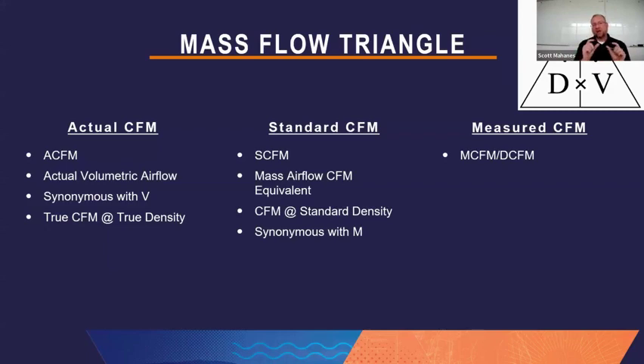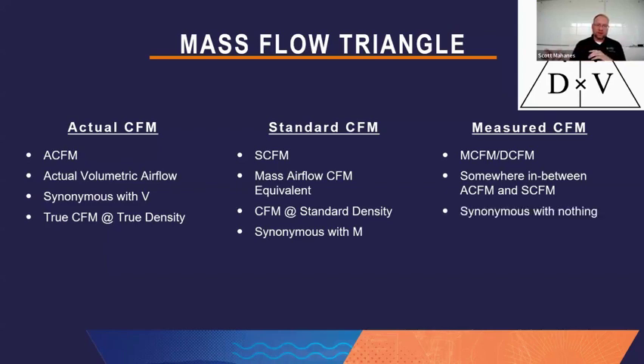And the displayed value that's on that meter doesn't always mean that's exactly what I have there, because if the temperature is different, then I definitely have to correct for that. And so oftentimes our displayed values on our tools are not exactly an accurate measurement because we have to consider the density at the time we do that test. And what ends up happening is this value comes in somewhere in between the ACFM and SCFM value. Why? Because it's partially compensated and not fully compensated. And in the end of the day, it ends up being synonymous with nothing on the triangle. It's kind of a bogus sort of number.